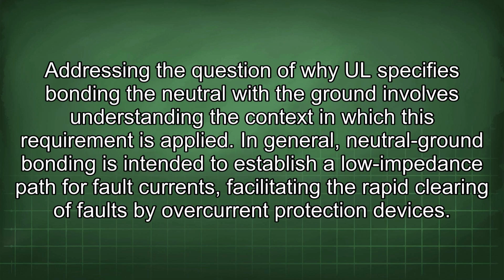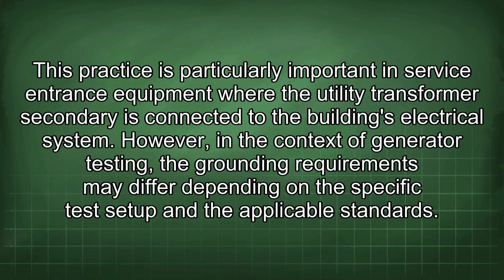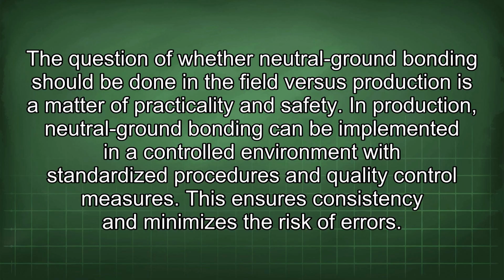Addressing the question of why UL specifies bonding the neutral with the ground involves understanding the context in which this requirement is applied. In general, neutral ground bonding is intended to establish a low impedance path for fault currents, facilitating the rapid clearing of faults by overcurrent protection devices. This practice is particularly important in service entrance equipment where the utility transformer secondary is connected to the building's electrical system. However, in the context of generator testing, the grounding requirements may differ depending on the specific test setup and the applicable standards. The question of whether neutral ground bonding should be done in the field versus production is a matter of practicality and safety.